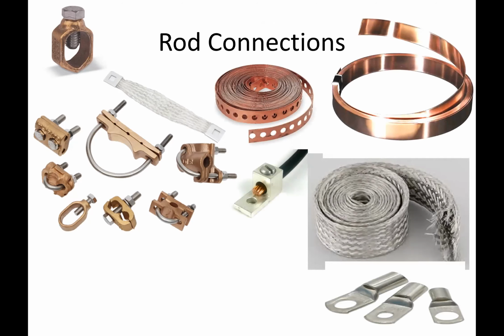Okay, what wires are we talking about? On the upper left and upper right corner is copper strapping — that's my favorite method of connecting a ground. It's thick, it's 100% copper, and conducts a lot of current if I need it to. In the middle you have what's known as copper hanging strap — basically steel strap that's been flashed with copper. It's got holes perforating it that you can use to hang copper pipe in your house or establishment, and it also is a good conductor to ground.